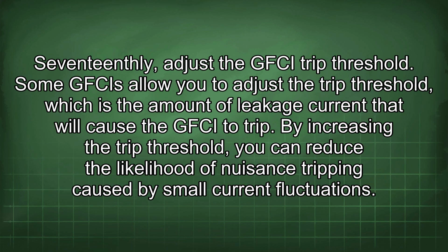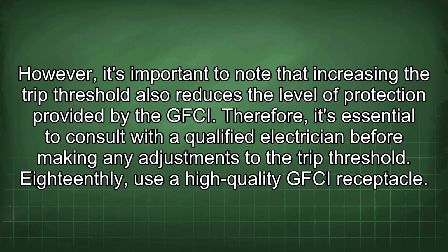17thly, adjust the GFCI trip threshold. Some GFCIs allow you to adjust the trip threshold, which is the amount of leakage current that will cause the GFCI to trip. By increasing the trip threshold, you can reduce the likelihood of nuisance tripping caused by small current fluctuations. However, it's important to note that increasing the trip threshold also reduces the level of protection provided by the GFCI. Therefore, it's essential to consult with a qualified electrician before making any adjustments to the trip threshold.